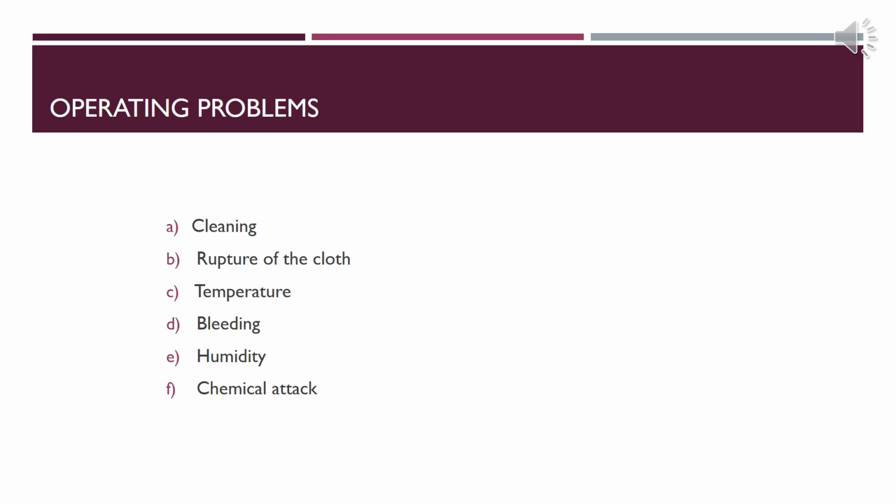The greatest problem inherent in cloth filters is the rupture of cloth, which results from shaking. It is often difficult to locate ruptures, and when they are found, the replacement time is often considerable.